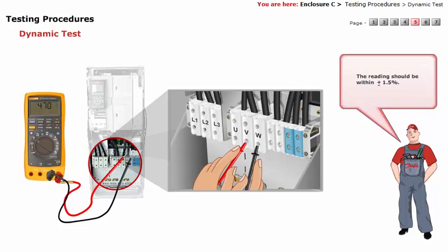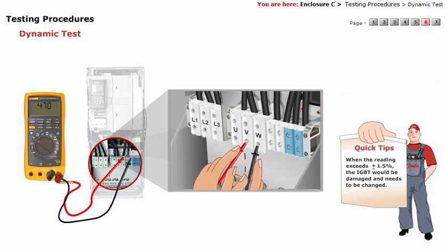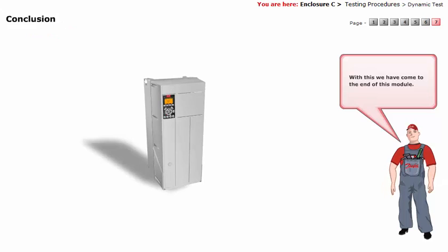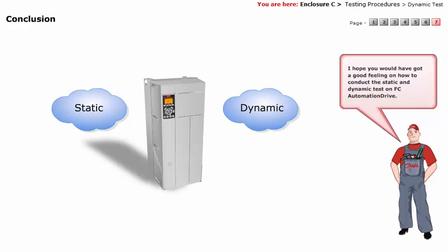The reading should be within plus or minus 1.5 percent. When the reading exceeds plus or minus 1.5 percent, the IGBT would be damaged and needs to be changed. With this, we have come to the end of this module. I hope you would have got a good understanding of how to conduct the static and dynamic test on FC Automation Drive.